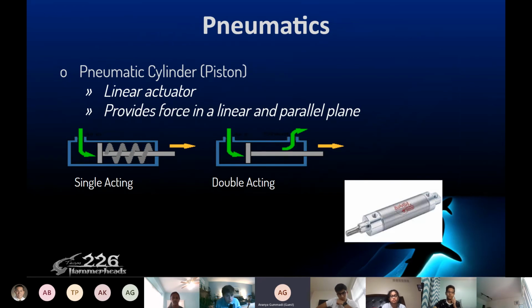So these control valves that manage the airflow, they direct air to cylinders where the air pressure causes the cylinder shaft to move either in or out. These cylinders and the valves that control them come in two types, single action and double action, which you can see in diagrams as I explain both.